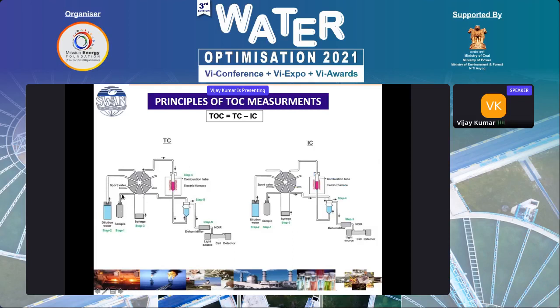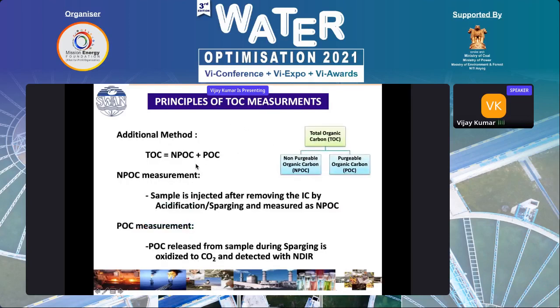Everything is automatic, and an 8-port valve is there. The sample is sucked by the syringe and pushed into the 680 degree catalytic conversion, which converts everything into CO2, detected with NDIR. That is the TC measurement. For IC, the sample is injected into the IC reaction vessel, where phosphoric acid converts IC into CO2 and it is liberated. So TC minus IC is how you measure.